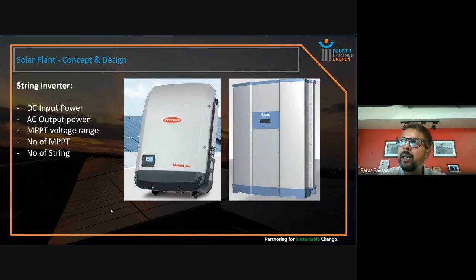A string is a combination of multiple modules connected with the inverter. A series and parallel connection is used to connect with the inverter. When we connect PV modules in series, that series we call a string. Normally in our terminology, we have a 20-module string, mostly in a range of 18 to 20 modules, and the voltage makes the final decision: how much VMP is defined in the module, and what total VMP can be handled by the inverter.